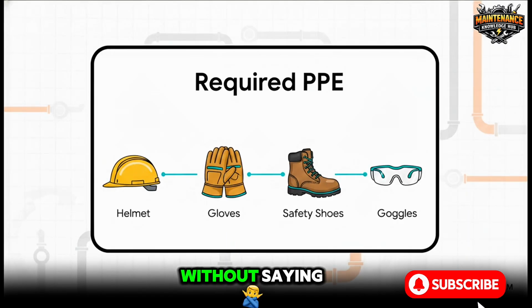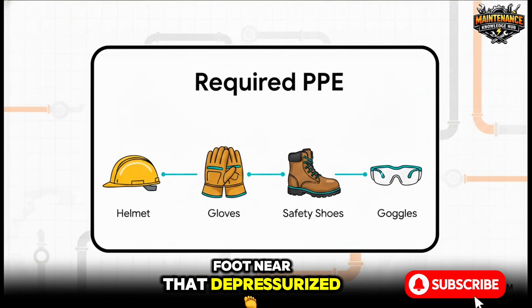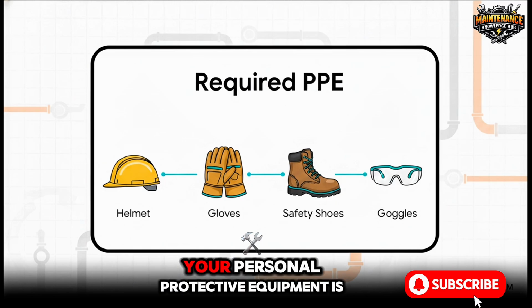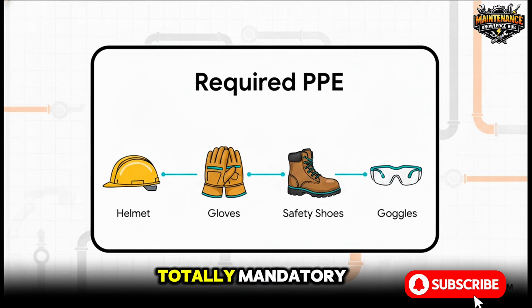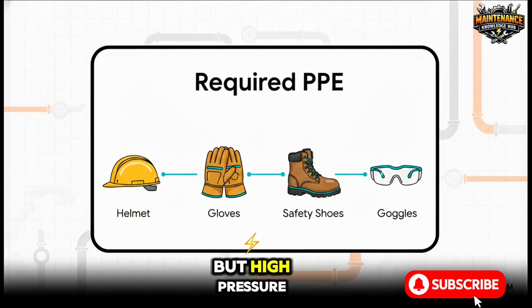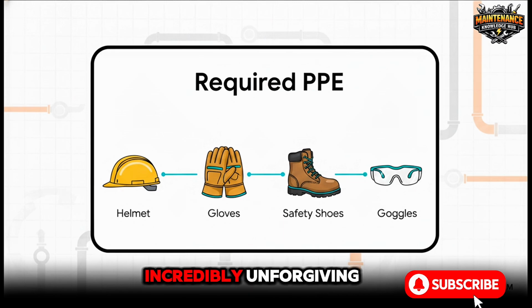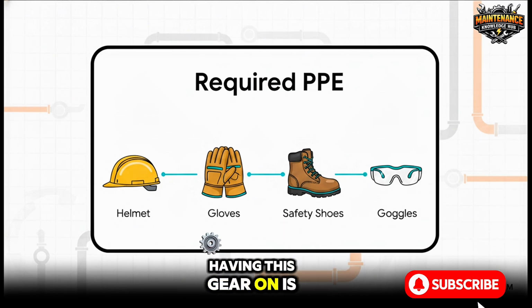And hey, it goes without saying, but before you step foot near that depressurized, locked-out boiler, your personal protective equipment is totally mandatory. Helmet, gloves, safety shoes, and goggles. Sounds simple? Yeah, it is. But high-pressure steam and boiling water are incredibly unforgiving. Having this gear on is just non-negotiable on the plant floor.